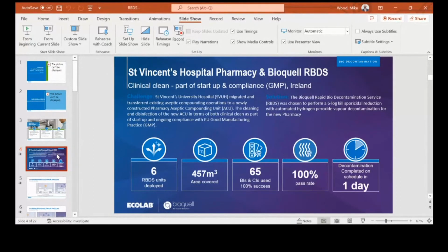Within the enclosure, we used our Clarus C generators. The area was 457 meters cubed. We used 65 BIs and CIs, so chemical indicators, and the BIs are the Geobacillus stearothermophilus endospore. 100% success rate, and we deactivated them all. 100% pass rate, and the decontamination was completed on schedule in 1 day.